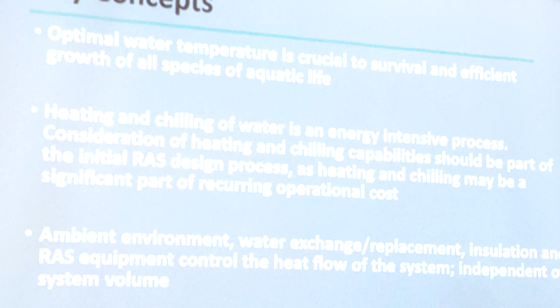And lastly, I have a major misconception I think I want to dispel today. System volume is a small part of how we size for heating and chilling loads, but it's not the only thing. Our company, we get a lot of requests saying, I've got a 10,000 gallon tank, what kind of chiller do I need? And unfortunately, that doesn't really tell us much of what we need to do to adequately size that for your facility or operation. Things like the environment, the amount of replacement water, insulation, your whole filtration system, all that equipment, have much more impact on the heating and chilling loads than just the volume of water.